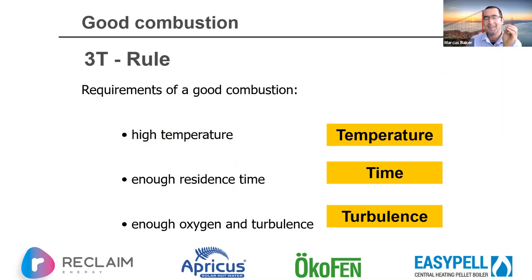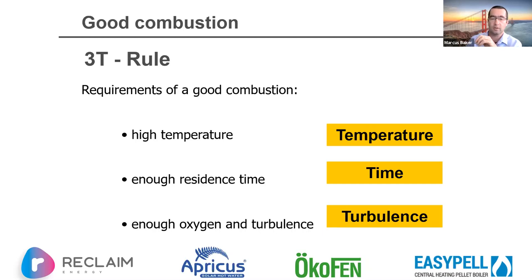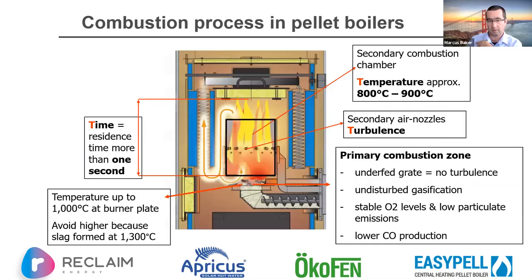There's a good rule called the 3T rule: high temperature for good combustion; enough residence time, which is very important to get full secondary combustion; and turbulence, ensuring you have enough oxygen mixed so you get good fuel-to-oxygen ratios and are optimizing heat transfer.